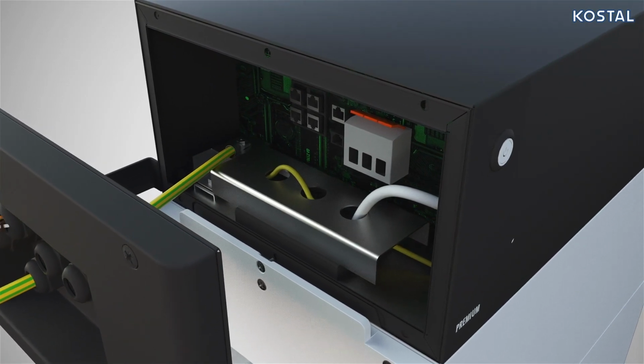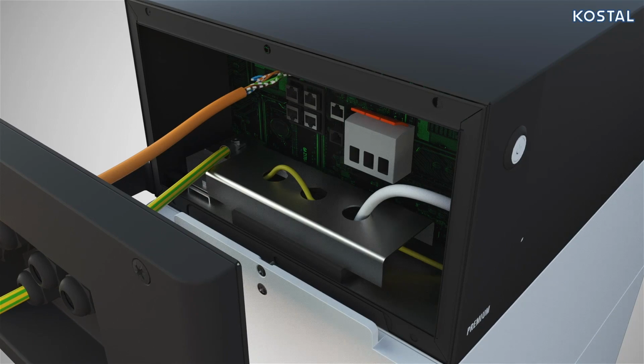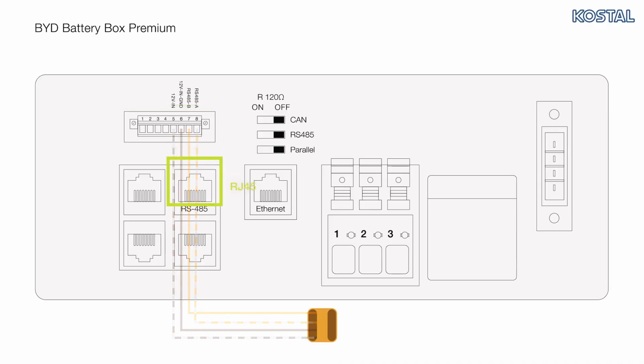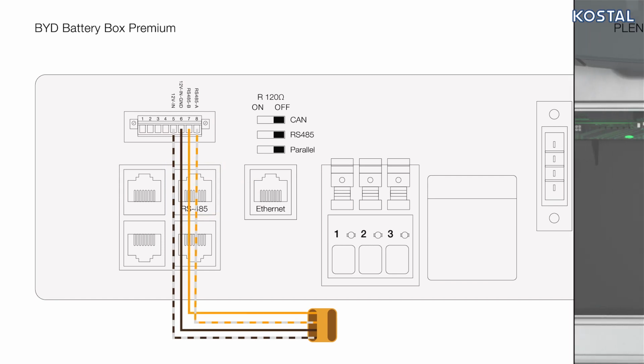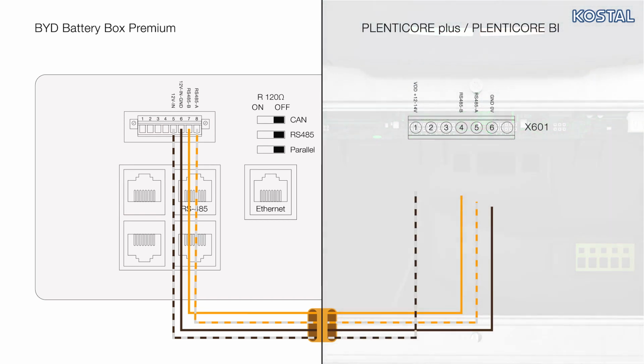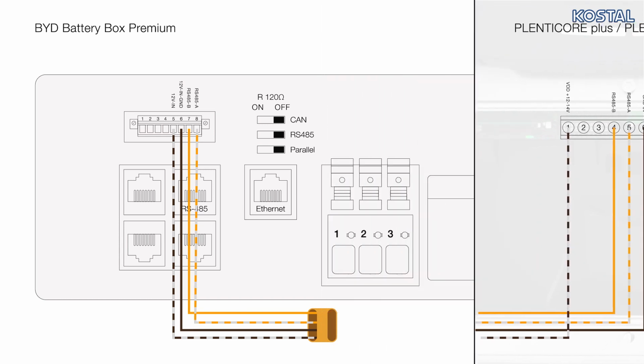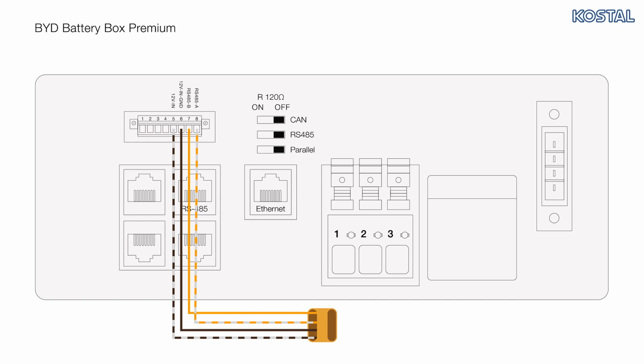Now connect the communication cable to the BYD Battery Box at the terminal block connector. Alternatively, you can also use the RJ45 socket. Connect the other end of the cable to the X601 terminal of the PLENTICORE. Note, we recommend a network cable of category 5E or higher. Please ensure that the 3 dip switches for the terminating resistors are in the on position, on left.